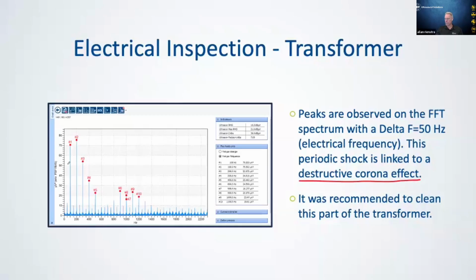And why did we determine it was destructive corona? Because we'd monitored it over time. We might have detected it a few months prior, and now that we've let it go for 2 or 3 months, we can see that the amplitude in the y-axis has become elevated. And so as it elevates over time, we know that we're moving from nuisance corona into destructive corona. The recommendation was to clean the component that we'd isolated and then come back and check it again to see. There was no heat being generated by this defect.